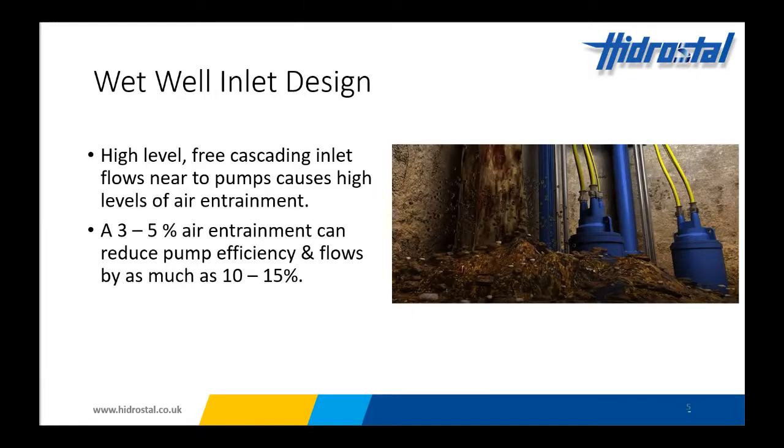If we look at the wet well inlet design, high level free cascading inlet flows near to pumps can cause a high level of air entrainment. It's important to note that 3 to 5% air entrainment can actually reduce the published efficiencies and flows of pumps by as much as 10 to 15%. Another important thing to note, though, is that air entrainment efficiency losses during a short duration when you're cleaning a sump are far outweighed by the larger energy savings that you can realize through sustained reduction of pump blockage that low level operation and sump cleaning can give.